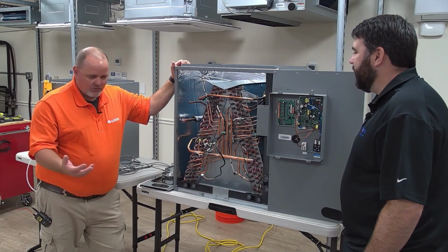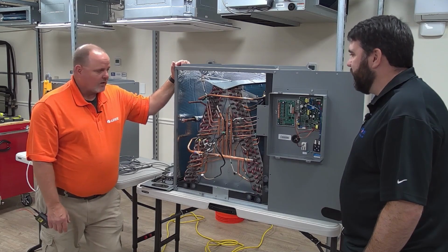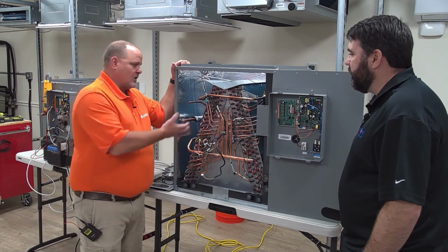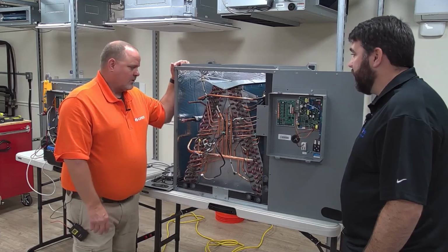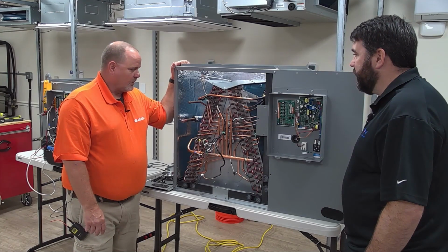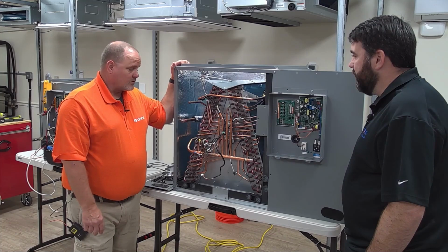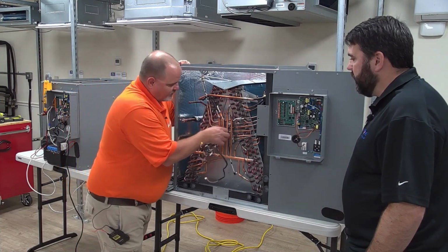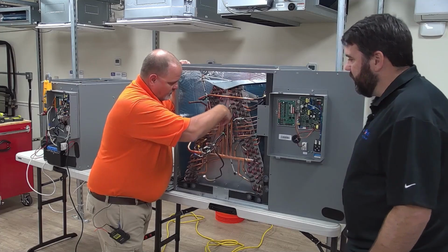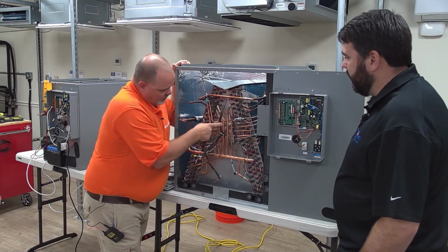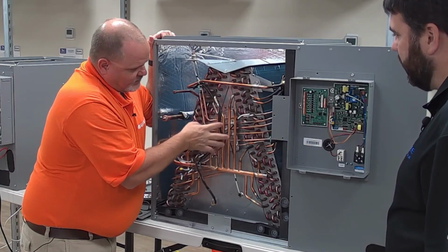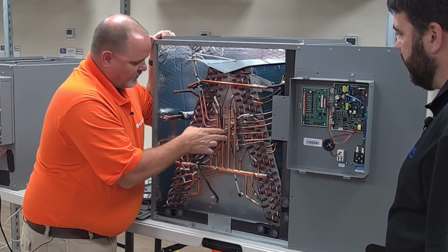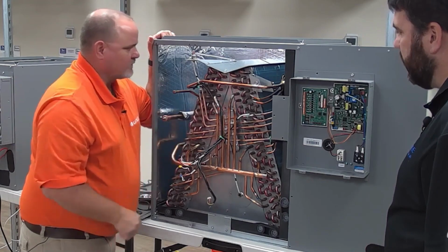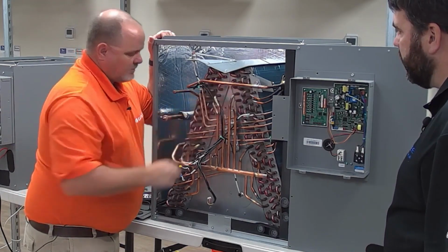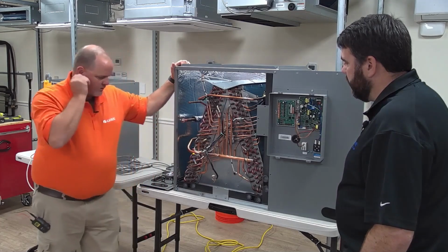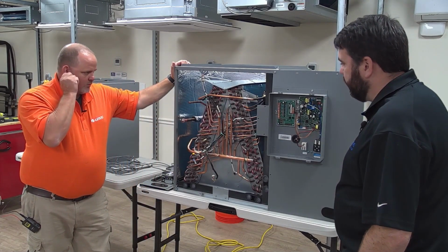Get it all ready. And I know the coils are not light with that coil in there, but it's not going to be that much lighter just having the coil. So GREE's proud of their coils, and they're proud of the way they do things, and I actually like the way they do it too. It's hard to see, but you can kind of see in here. I like the fact that they strap every single one of those distributors in place. Yeah. There's no vibration here. That's not happening. We're not going to have a pipe sitting there wiggling and causing us a leak. Same with up here. It's all strapped in place. They do a great job of making sure things are tight. Yeah, they do. So, yeah.